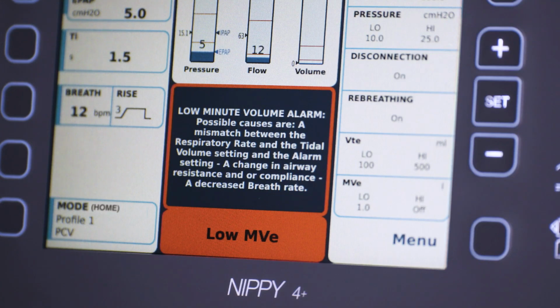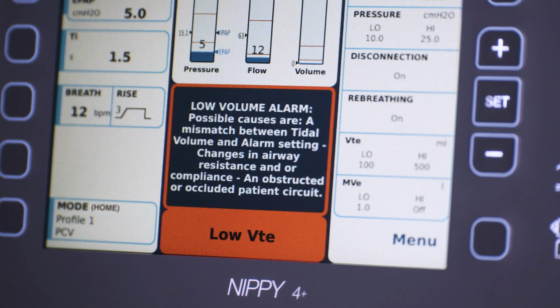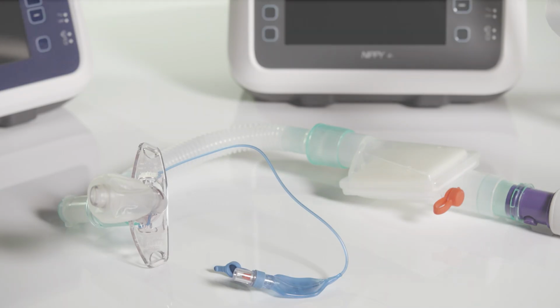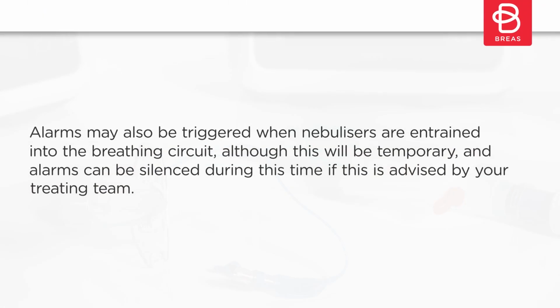A low minute ventilation or low tidal volume alarm may indicate an unintentional decannulation. Alarms may also be triggered when nebulizers are entrained into the breathing circuit, although this will be temporary, and alarms can be silenced during this time if this is advised by your treating team.